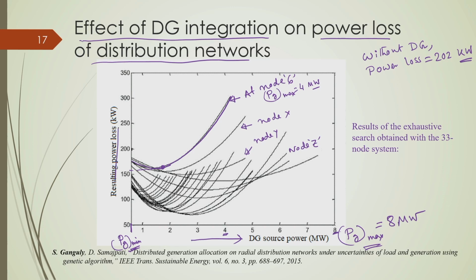There are 33 characteristics, each following a similar pattern: connecting a DG at a particular location initially reduces the network power loss, reaches a minimal point, and then the loss starts increasing beyond that. We consider this resulting total network power loss with DG integration at each and every location of the distribution network, and the pattern is the same. Some buses stop at certain points since we considered different PG max values for each bus, which is why they terminate at different points.